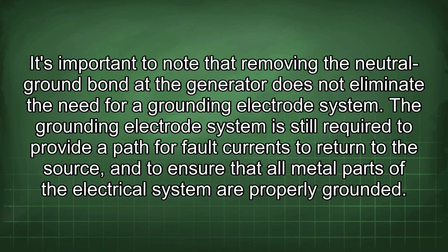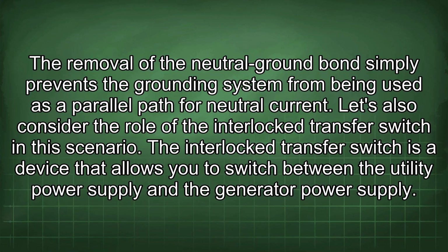It's important to note that removing the neutral ground bond at the generator does not eliminate the need for a grounding electrode system. The grounding electrode system is still required to provide a path for fault currents to return to the source, and to ensure that all metal parts of the electrical system are properly grounded. The removal of the neutral ground bond simply prevents the grounding system from being used as a parallel path for neutral current. Let's also consider the role of the interlock transfer switch in this scenario.